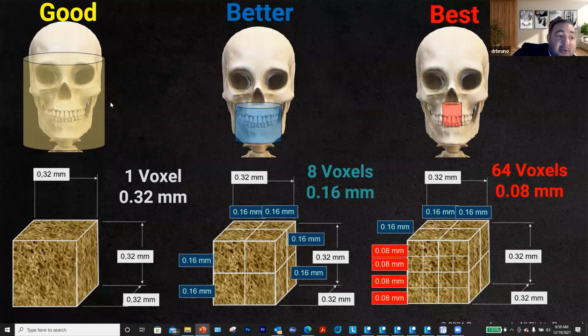So remember, when you take a larger field of view with your X800, and now you're dealing with a voxel of 0.32 millimeters, which means 320 microns, in the same area, if you were to acquire an image with a smaller field of view, 4x4, you would have 64 voxels displaying the same amount of information. So please understand this: your ability to display detail is going to be related to those numbers.